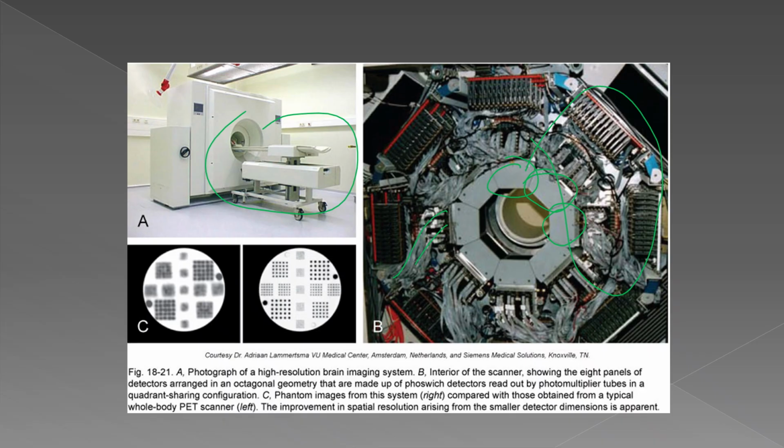And that's allowing those PM tubes to communicate that are opposite of each other or that are next to each other so that it can detect all of those annihilation photons. It has all the circuitry for not just sequencing timing, but also the time of flight and the timing window to make sure that it was able to do that.